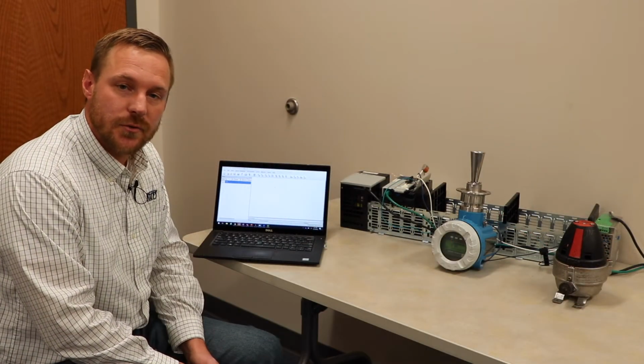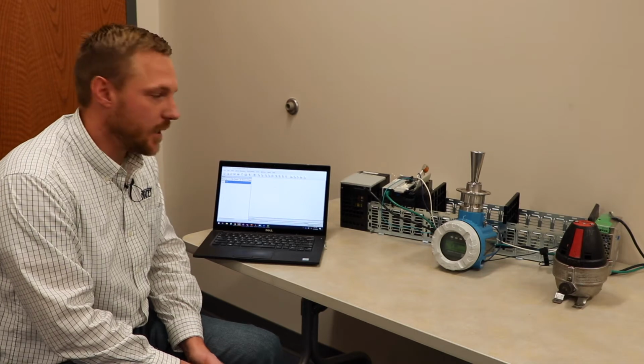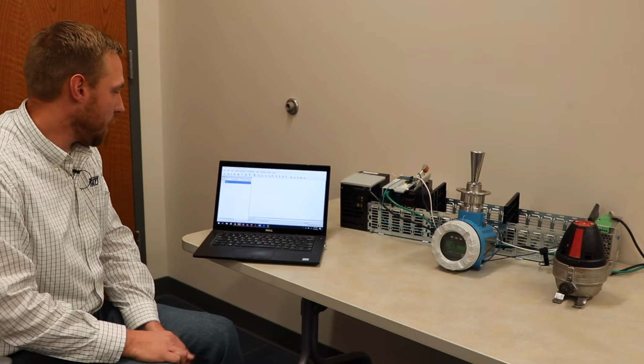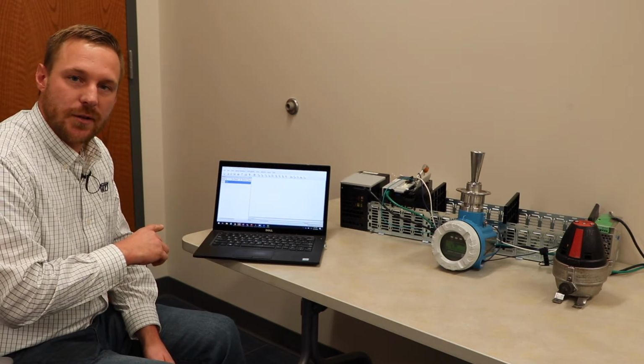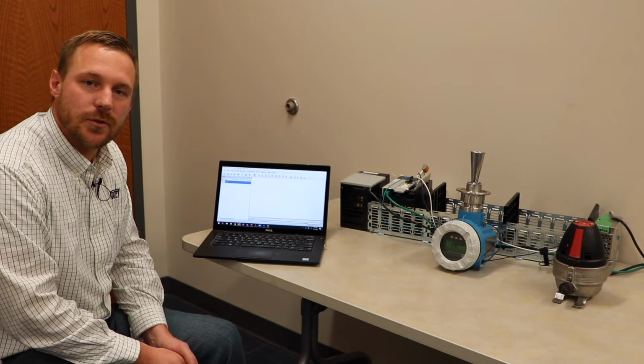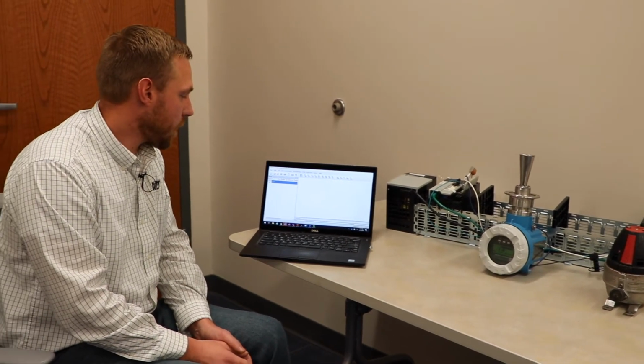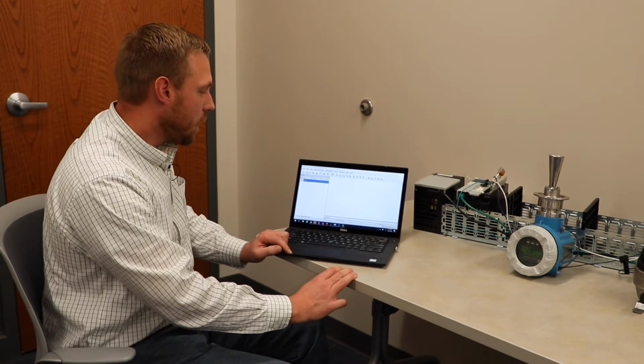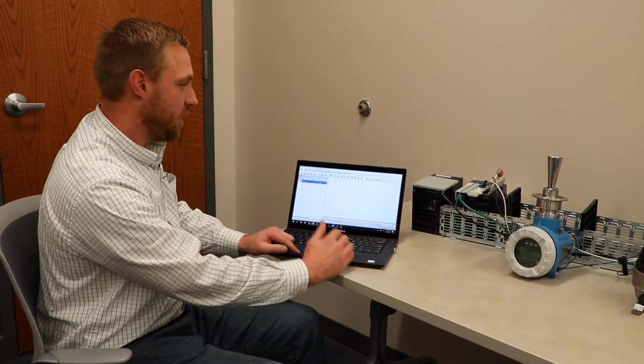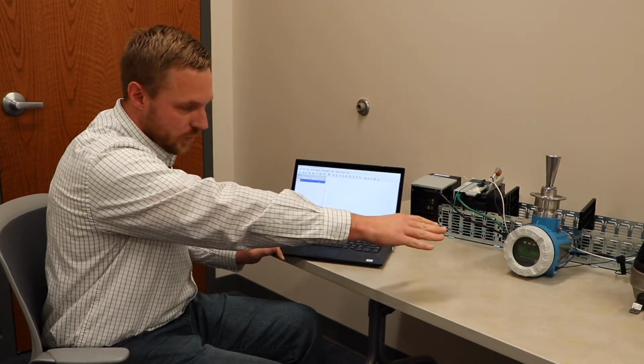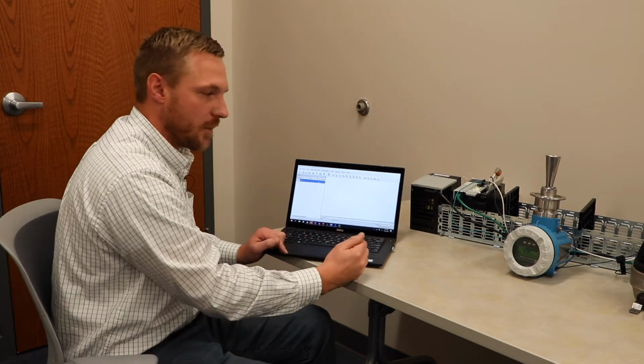If I was dialing into a plant's control system, I would need a VPN connection in order to get on their secure network. In this case, I don't, since I'm currently on the same connection. Once I'm online, I'll then use my software for communicating with that control system. I'm using FieldCare to do this. There are other products out there that can be used to communicate, but I use FieldCare for this. How we start out is we start out as the host PC, and then through some steps, we'll make our way through this control system in order to get to the instrument and be able to configure it.